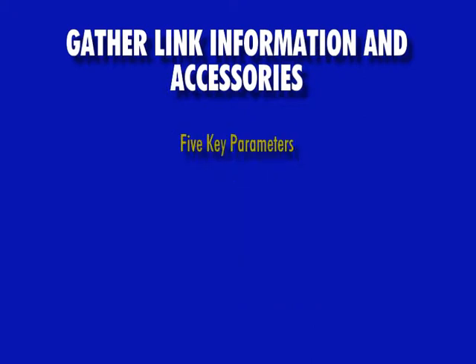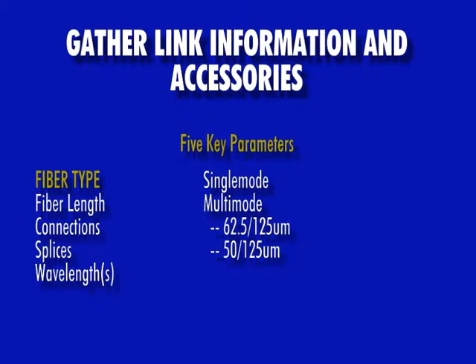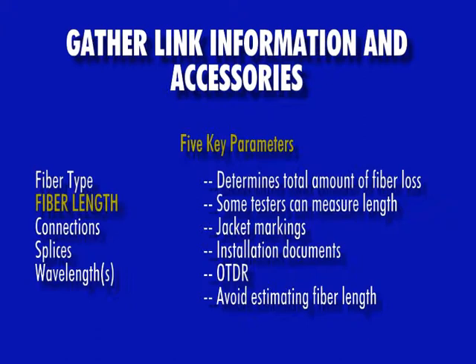There are five key parameters that apply to any fiber optic test. First is the fiber type, which will be either single mode or multimode — in the case of multimode, either 62.5 or 50 micron. Next is fiber length; it is important to know how much fiber is in the link to determine acceptable loss. Some OWL testers, including the Fiber OWL 4, can measure end-to-end length automatically. Otherwise, the user can use jacket markings, installation documents, or other methods such as OTDR.